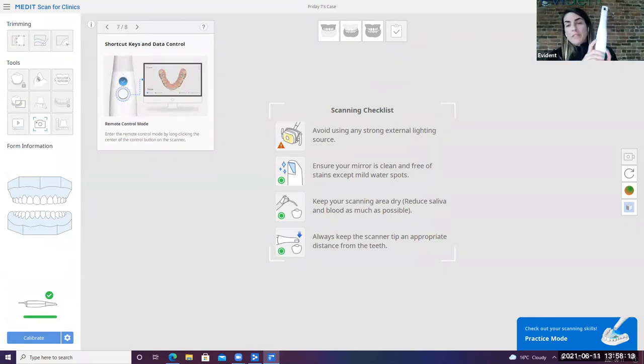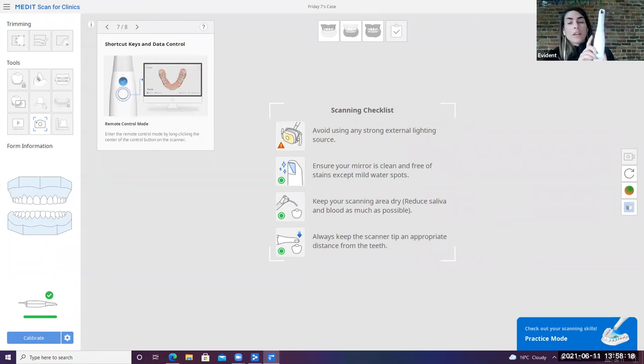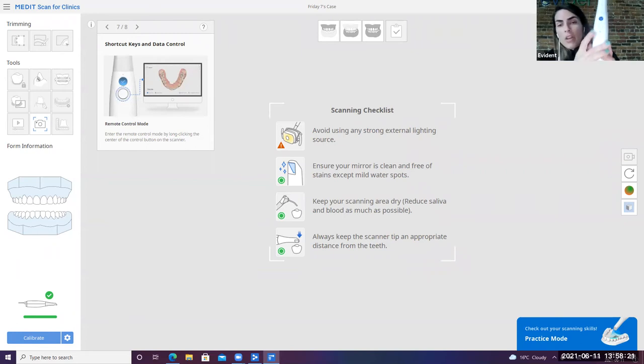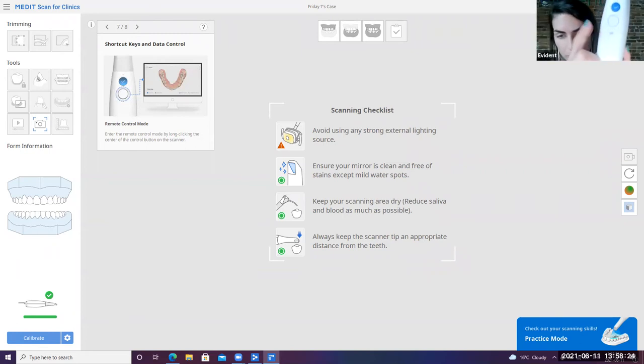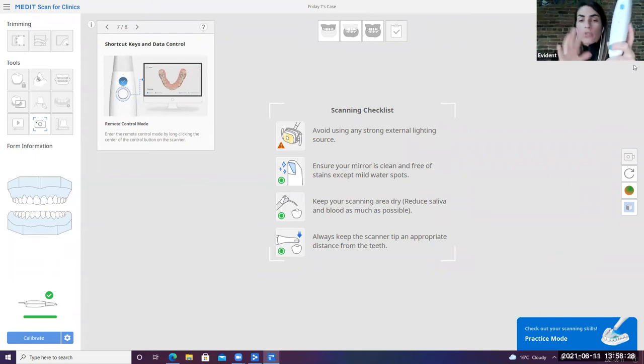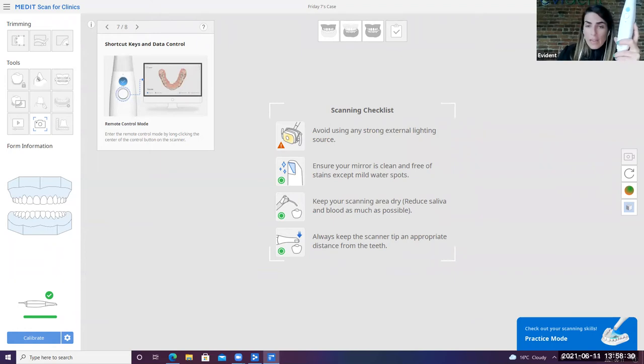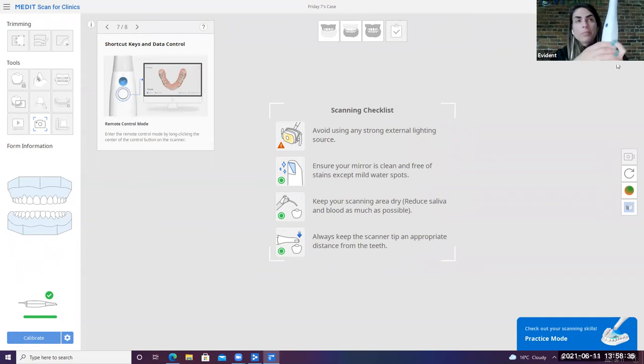So a couple of neat features with the 700. I don't know if you've been exposed to the 500 or the most of you, but with the 700, they've made some really cool updated features. So the 700 actually has a remote control button right here. So let's say, for example, if you're with a patient and you're alone, and you don't have the opportunity to go back to your mouse to access your screens, you can actually toggle through the system and rotate your scans using the remote control.